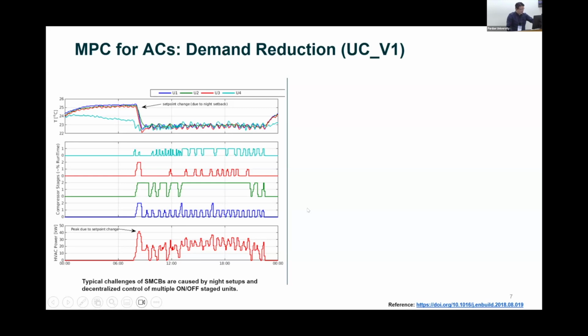And this is a big problem for a small or medium commercial building. Although it's not the load shifting problem, we have to eliminate this problem because, in order to pre-cool the space, the only way of making this happen is lowering the set point. And if this kind of scenario keeps happening, then we are increasing the building owner's demand charge. That doesn't really make sense.